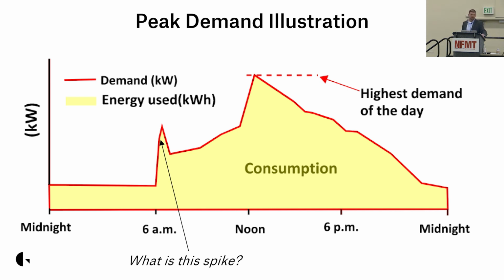We looked at this through commissioning and realized your facility's main demand charges are set between 6 and 7, dictated by your local jurisdiction - NES is our electrical system here in Middle Tennessee. So we staggered all the equipment to come on starting at 4:30, with different floors coming on at 4:45, then 5 o'clock. By staggering it out, we removed that first morning peak.